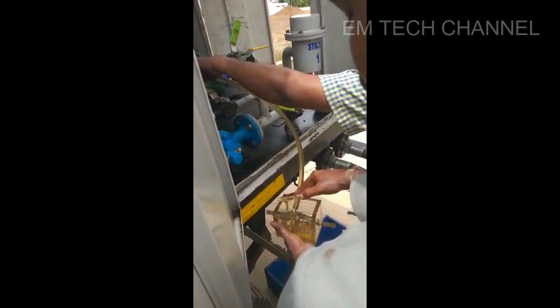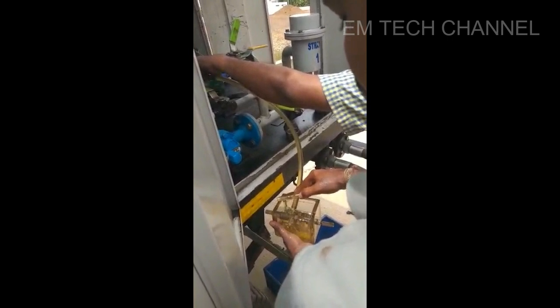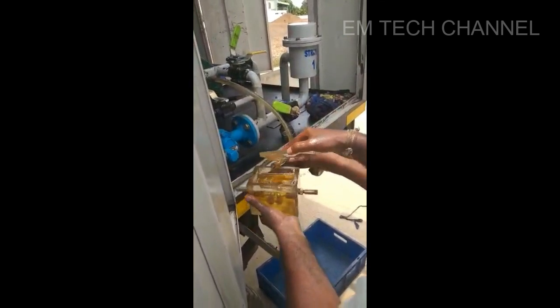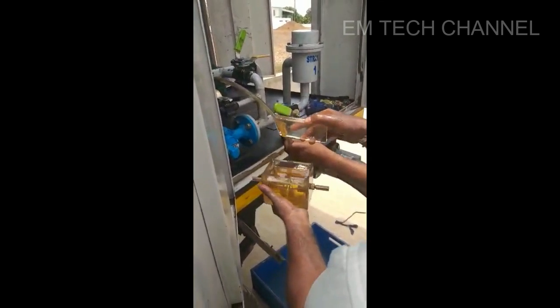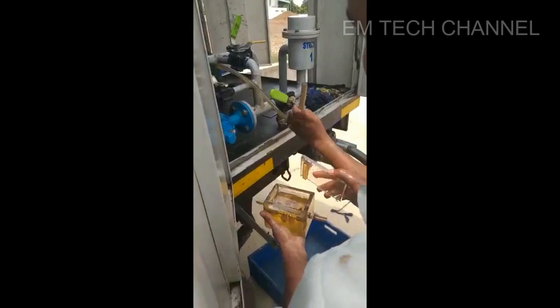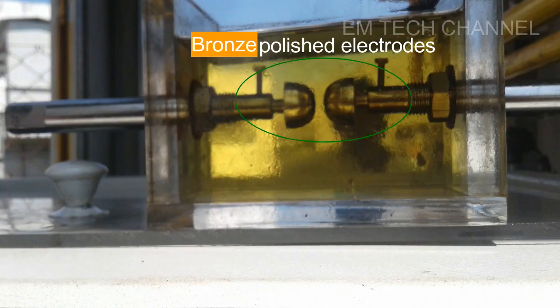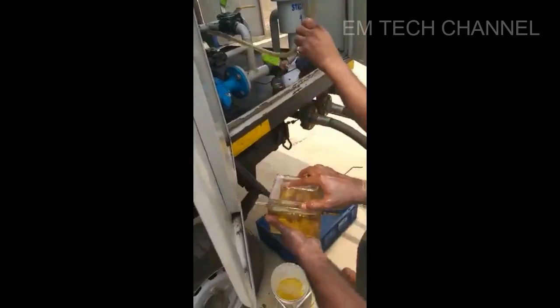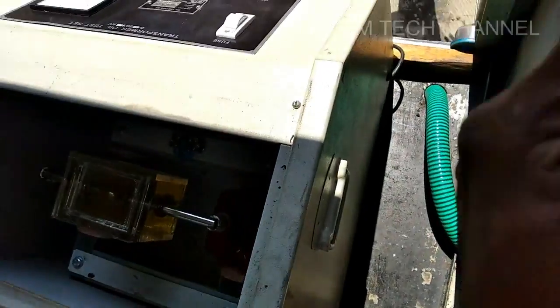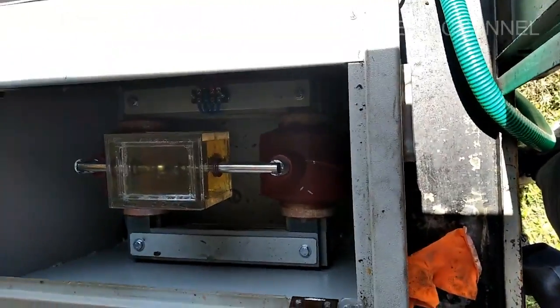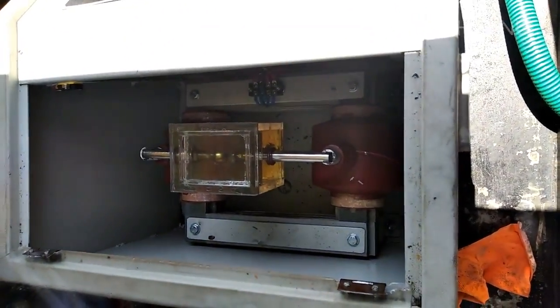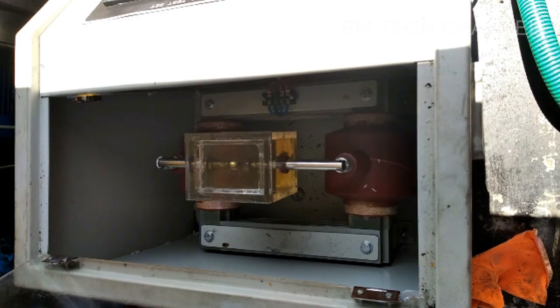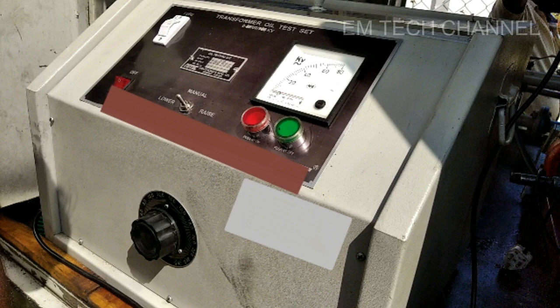See here, oil is being filled into the test cell, which is made up of rigid plastics in this case, and this test cell is also designed as per the standard, and the oil is filled up to the top so that the electrodes are fully immersed in the oil. Once the oil is filled, it is kept into the test kit designed as per the standard. You can see here, the supply will be fed to the electrodes by the 2 metal parts extending outside the test cell, and this is the test kit which is designed as per the standard with the custom made operation interface.